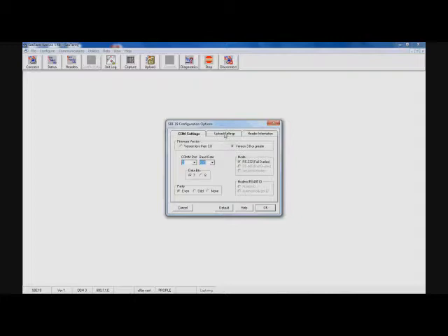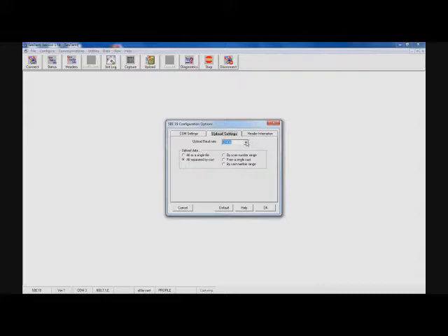The next thing we need to do is check the upload settings. Here we can select the upload baud rate, so how fast the data is streamed from the CTD to the computer. We'll set this at 38400, but your other options go from 600 up to 38400. Then there is how the casts are separated, whether they all come in as a single file or are separated by cast.